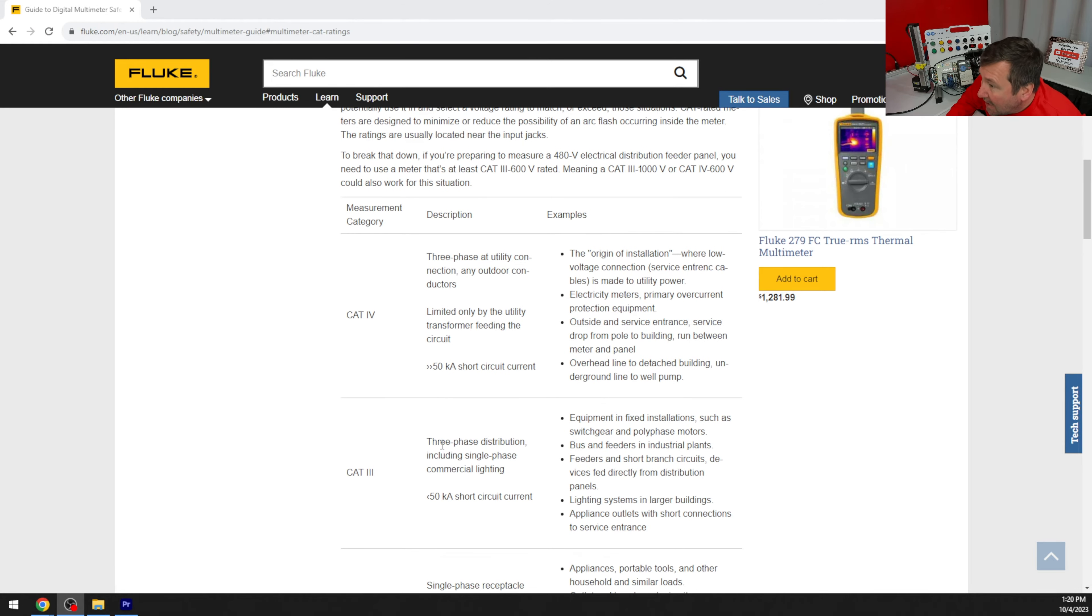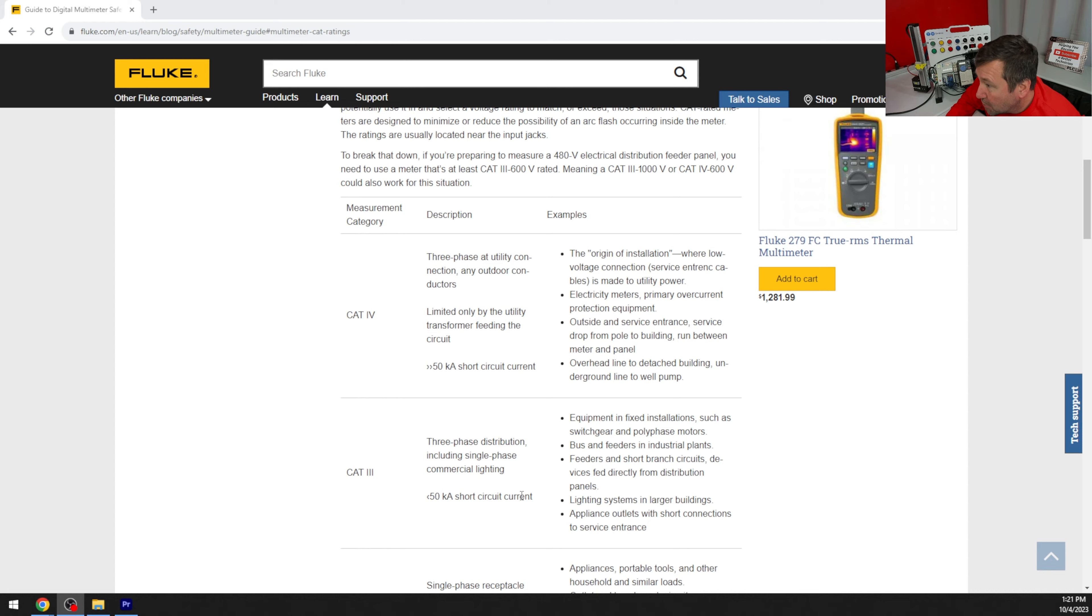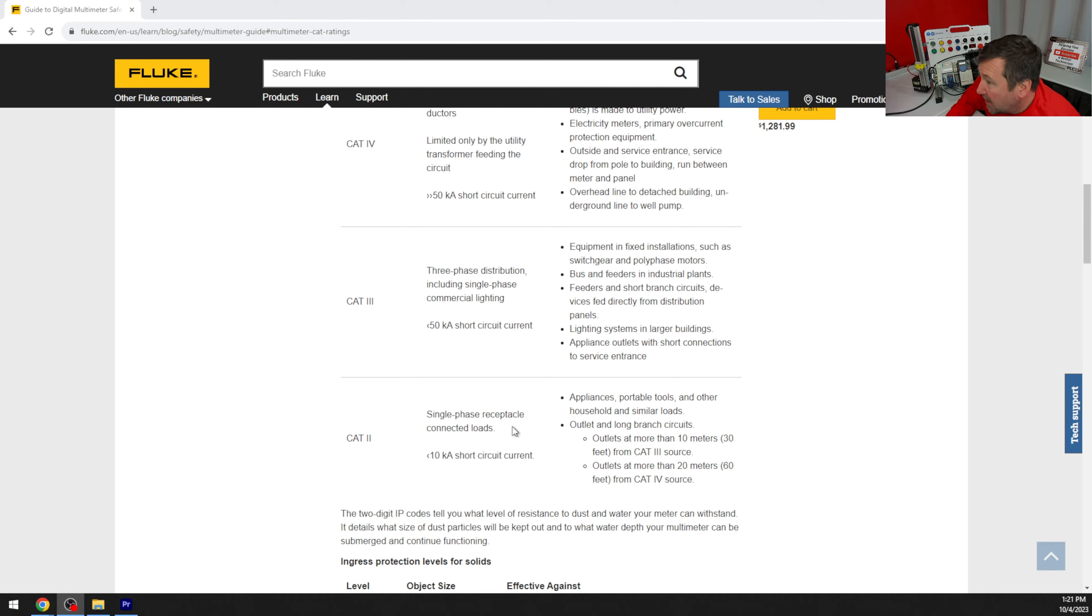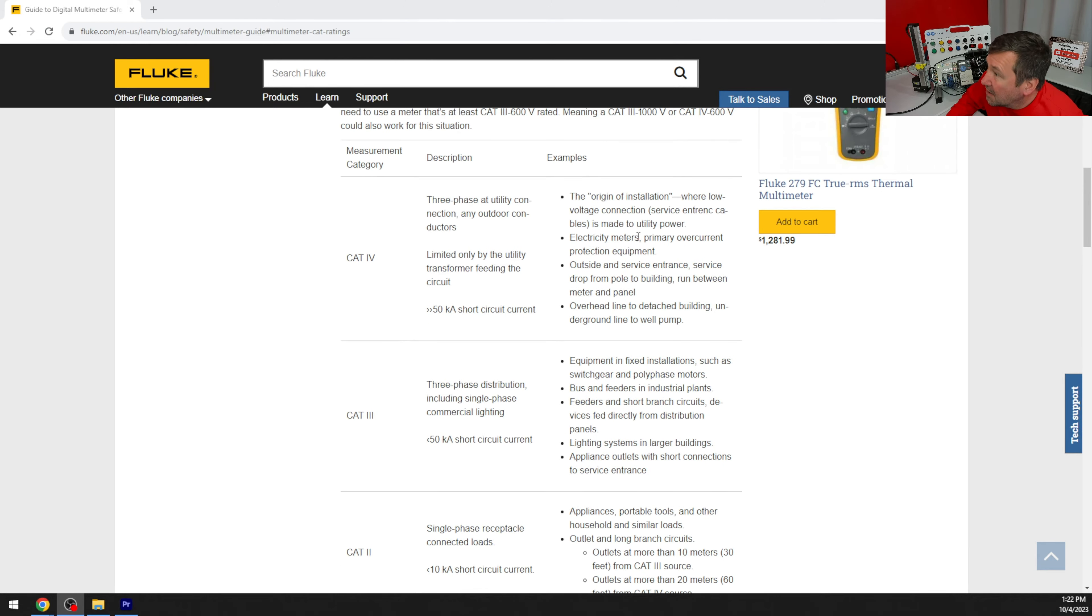And cat 3, three-phase distribution including single-phase commercial lighting, less than 50 kiloamp short circuit current rating. And we do have cat 2, and I don't see it very often, but that's for single-phase receptacle connections, less than 10 kiloamp. And they also give some examples on the right.